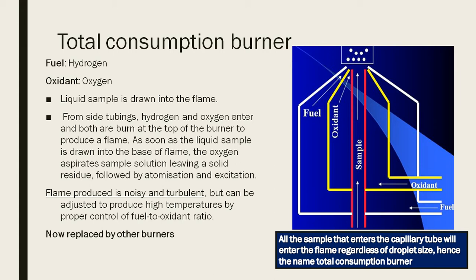Also, the total consumption burner has now been replaced by other burners because the flame produced is noisy and turbulent. Now, as you can see, all the sample that enters the capillary tube will enter the flame regardless of the droplet size, be it larger droplets or smaller droplets, hence the name total consumption burner.